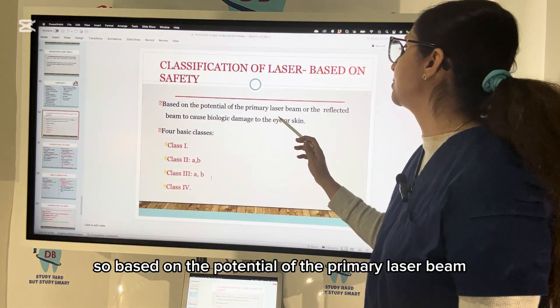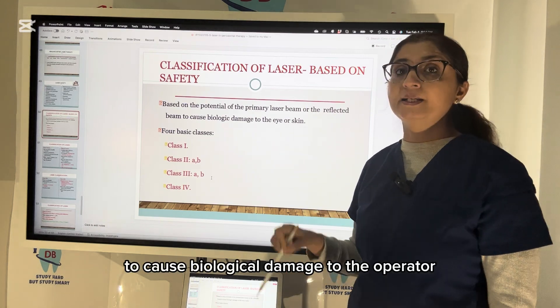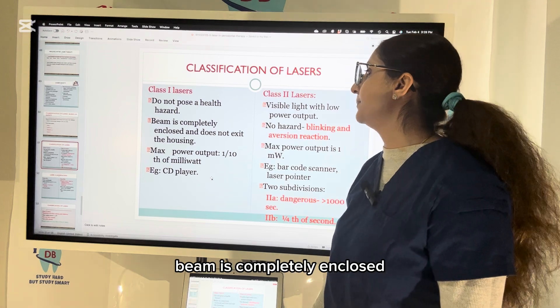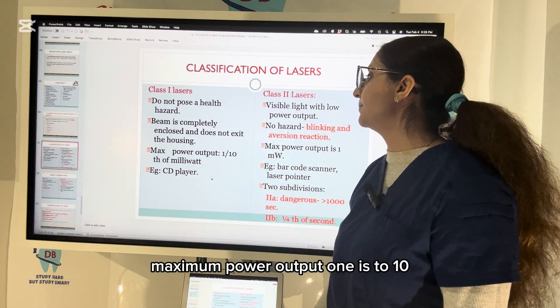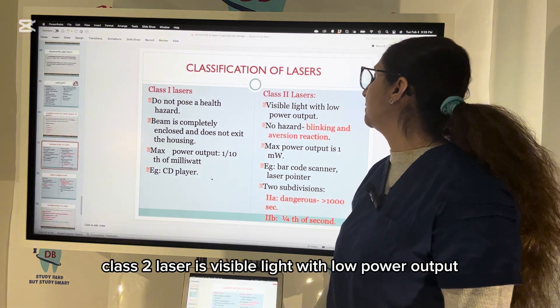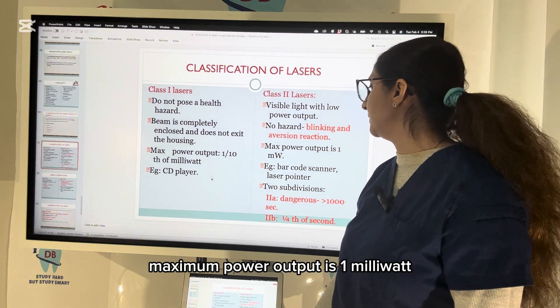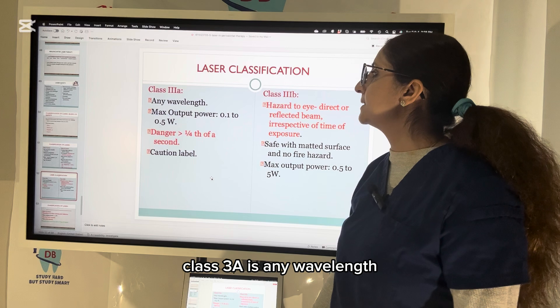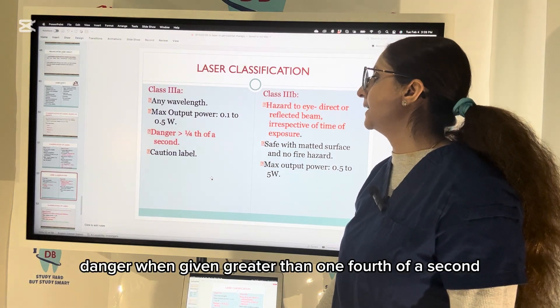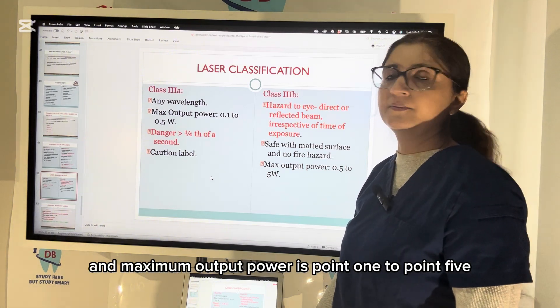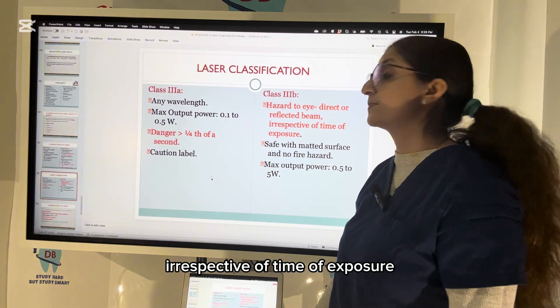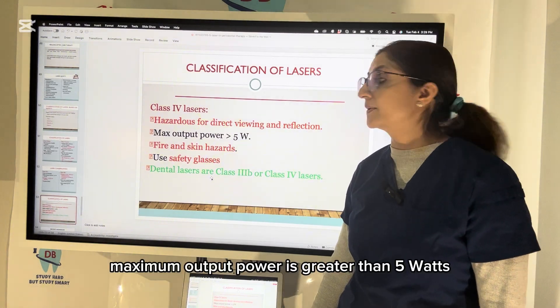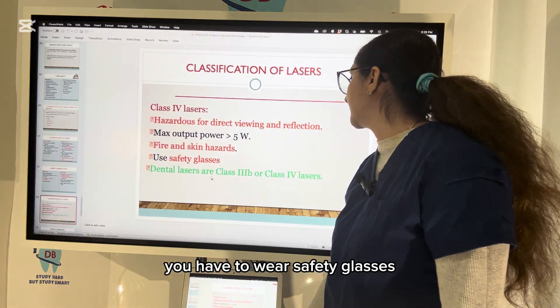Classification of lasers based on safety is determined by the potential of the primary or reflected laser beam to cause biological damage to the operator's eye or skin. There are four basic classes: Class 1 — no health hazard, beam completely enclosed, maximum power output 1/10th of a milliwatt; Class 2 — visible light, low power, no hazard but blinking and aversion can occur, maximum 1 milliwatt (2a: dangerous if given >1000 seconds; 2b: one-fourth of a second); Class 3a — any wavelength, dangerous if given >0.25 seconds, maximum 0.1–0.5 watts; Class 3b — hazard to eye by direct or reflected exposure irrespective of time, maximum 0.5–5 watts; Class 4 — very hazardous for direct viewing and reflection, maximum >5 watts, fire and skin hazard, safety glasses required. Dental lasers are Class 3b or Class 4.